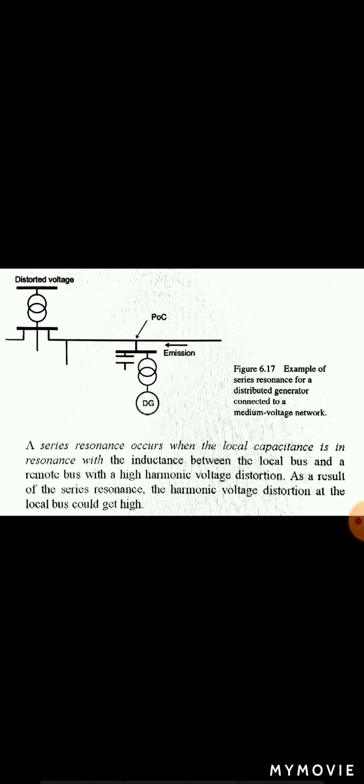A series resonance, you can see the series resonance diagram, occurs when the local capacitance is in resonance with the inductance between local bus and the remote bus with high harmonic voltage distortion. With the result of this series resonance, the harmonic voltage distortion at the local bus could be very high.